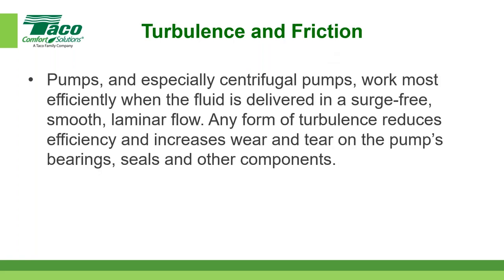And these centrifugal pumps work most efficiently when the fluid is delivered in a surge-free, smooth laminar flow, right? So as it comes around elbows, we don't want surges. We want laminar flow. Any type of turbulence reduces efficiency and increases wear and tear on the pump's bearings, seals, and other components. And then it can cause other problems, vibration, and premature failure. So really that piping, when you start signing off projects, take a look at that piping and feel comfortable with it. And as you gain experience, bring in the TACO rep if you'd like. He's got a hand in the cookie jar to make sure it goes in properly as well, so he can give you some guidance on some of that as well.